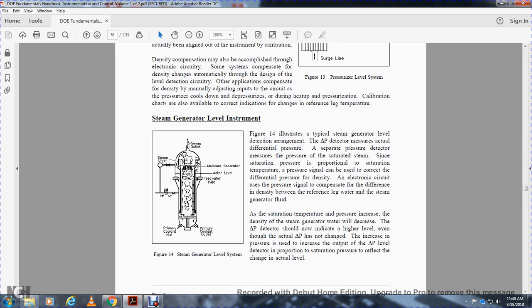Steam generator level indicator. Figure 14 shows the typical steam generator level detection arrangement, with a differential pressure detector and a separate pressure detector measuring the saturated steam pressure. The saturation pressure is proportional to the saturation temperature. The pressure signal is used to correct the differential pressure signal for the density in the electrical circuit. The pressure signal compensates for the difference in density between the reference leg water and the steam generator fluid.